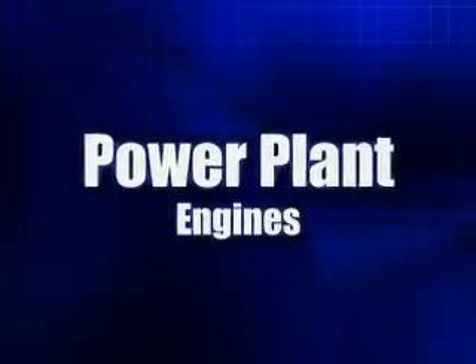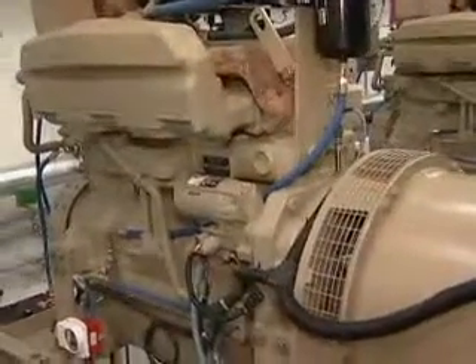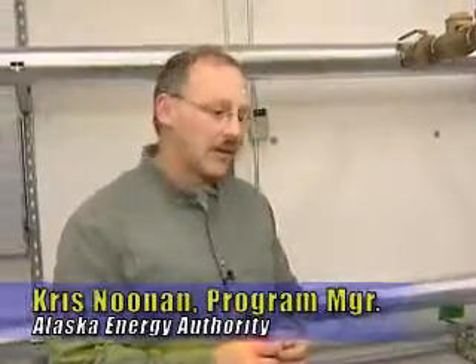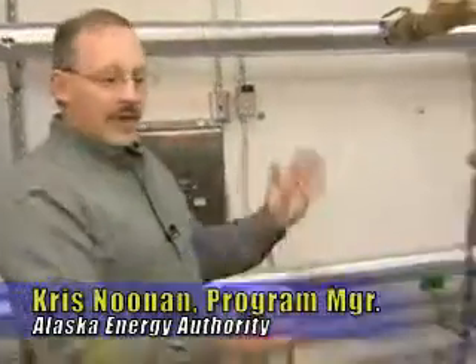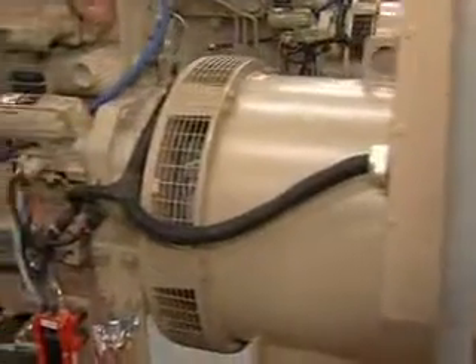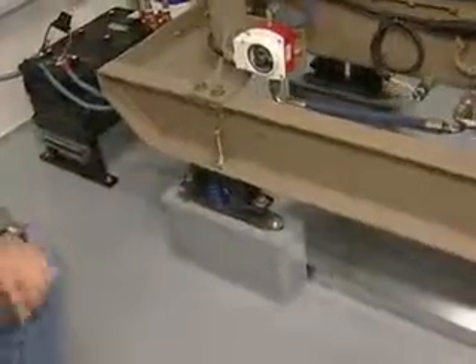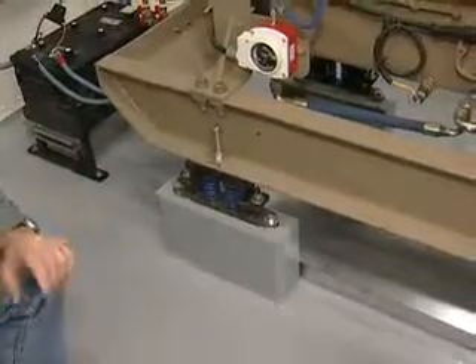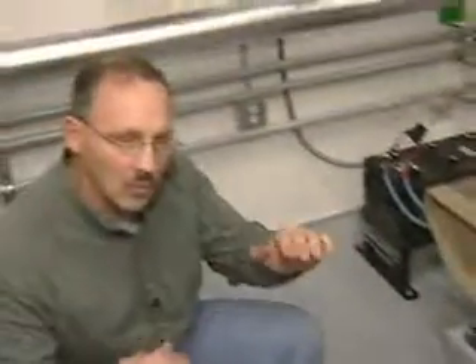What we're going to cover in this segment is basically the basic components that make up a generator set. We're going to go over from front to back everything that's on here so you get familiarized with what makes up a generator set. First off, we have the engine and generator that are on this unit. Basically, they're coupled together on a skid. The skid is mounted on these vibration isolators that are down here on the bottom. This helps absorb the shock of the engine starting and stopping and while they're running. They basically run on these vibration isolators and keep the vibration in the building down.